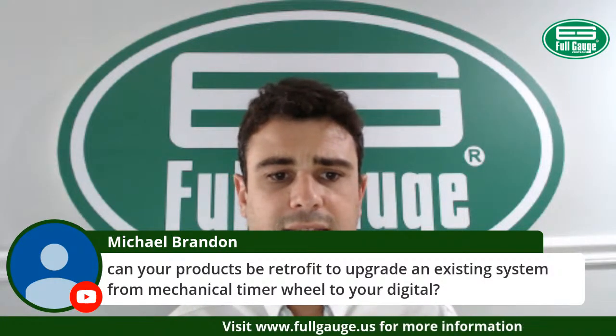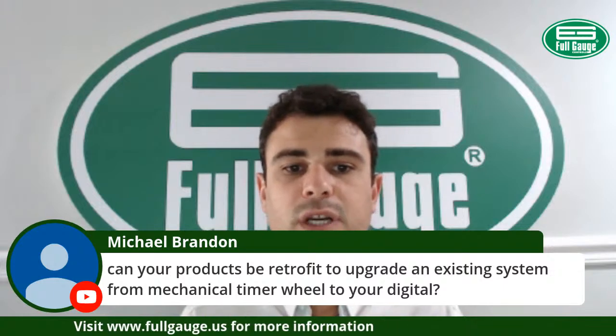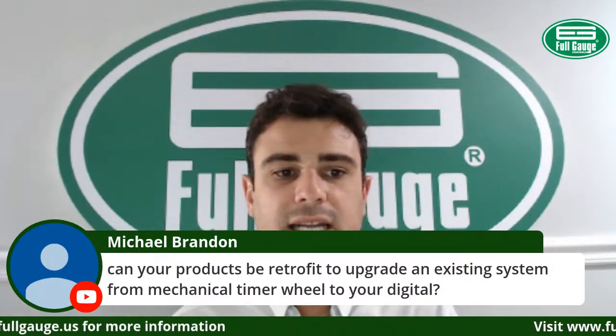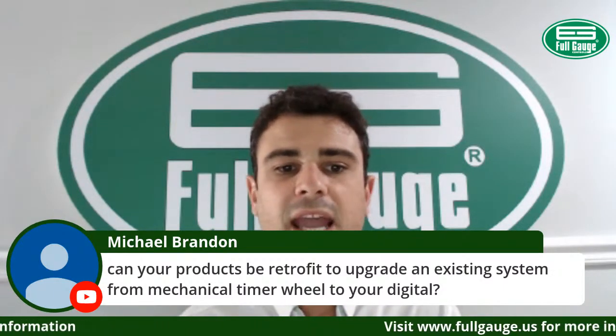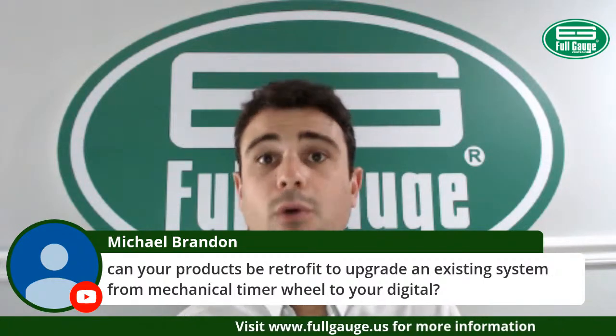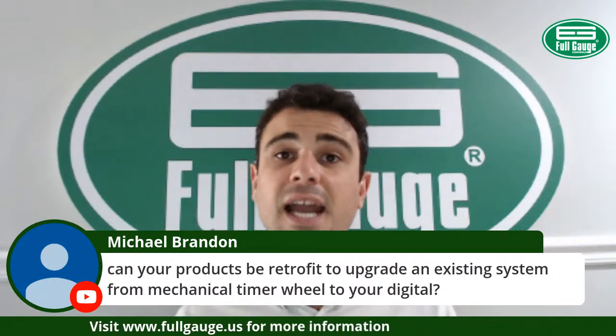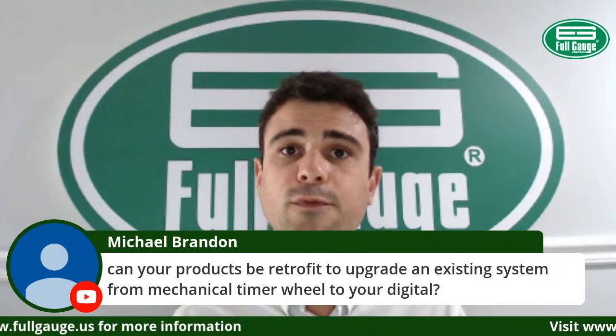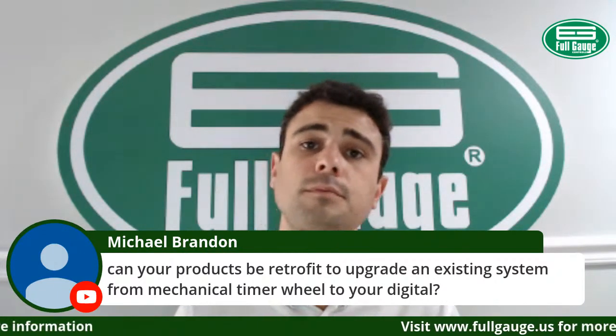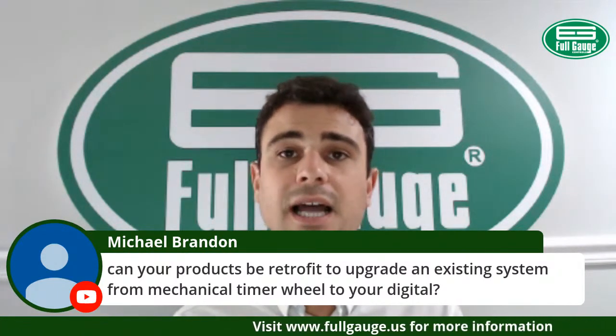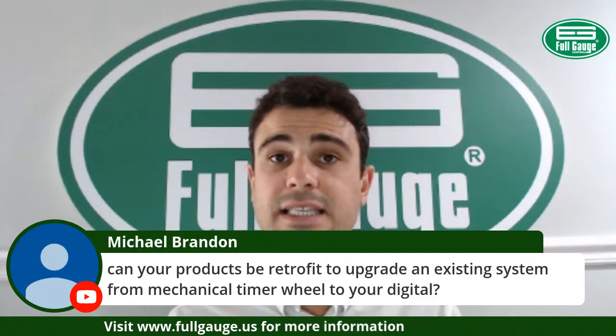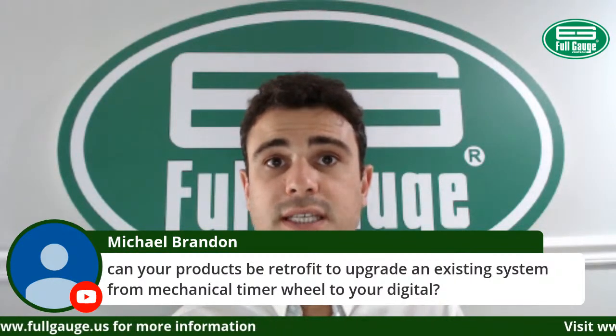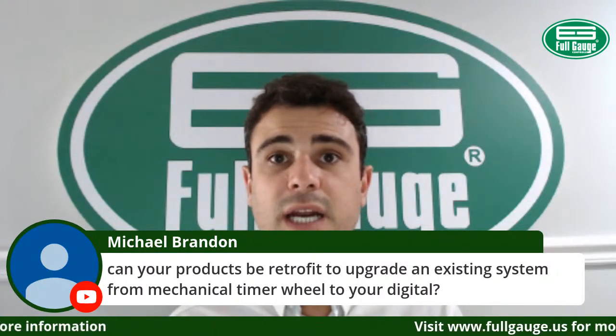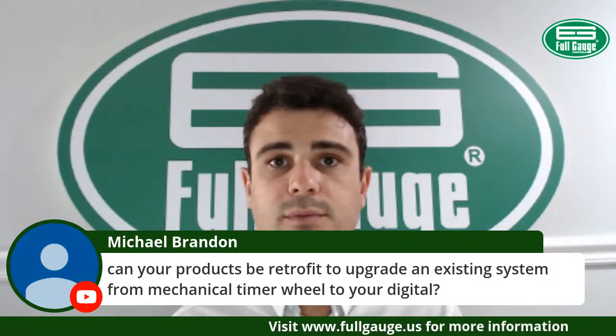So Michael is asking if the products can be retrofitted to upgrade an existing system from a mechanical timer to digital. Yes. In fact, our digital controllers, for example the TC900, will allow you to replace the thermostat, defrost timer, fan termination switch, and the defrost termination switch.